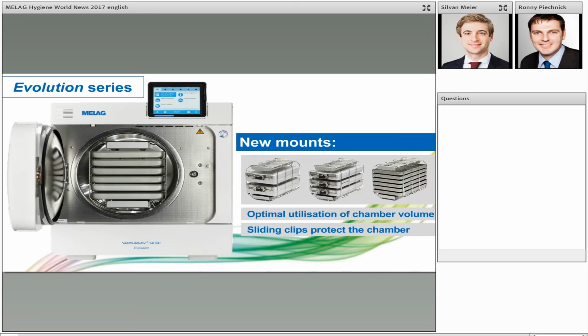6 regular trays, and in addition you have 2 narrow trays. So that allows you to load the autoclave with a total of 8 trays. If you prefer using containers, sterilization containers such as Melastore 100, you can load the autoclave with 3 containers and an additional 2 narrow trays. And the third solution that we provide is the Melastore 200, so the bigger containers where you can load 2 big containers with 2 narrow trays. So with these new mounts, it is now possible to load the autoclave more efficiently, which reduces the amount of cycles, and in the end, that saves you time and money.